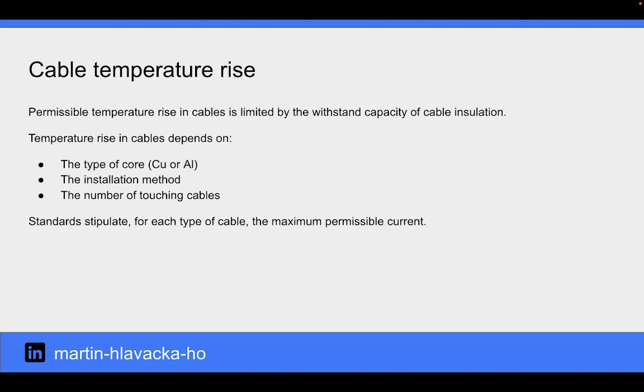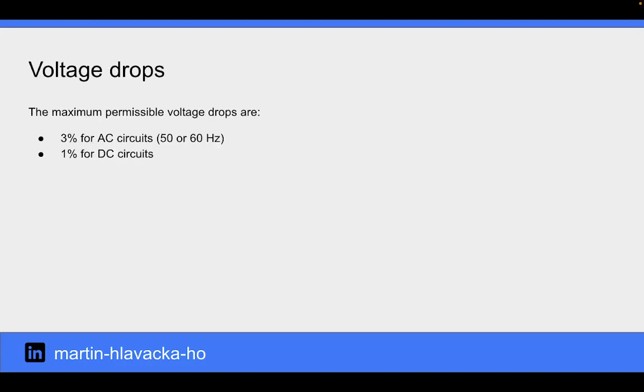Permissible temperature rise in cables is limited by the withstand capacity of cable insulation. Temperature rise in cables depends on the type of core, the installation method, and the number of touching cables. The maximum permissible voltage drops are 3% for AC circuits and 1% for DC circuits.